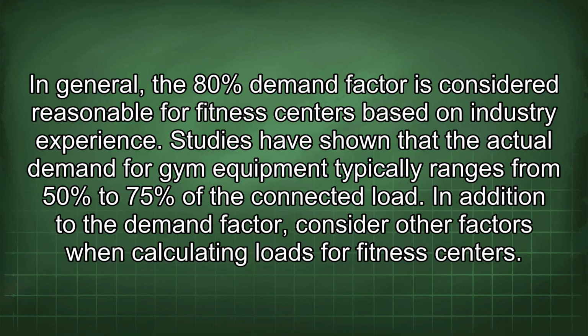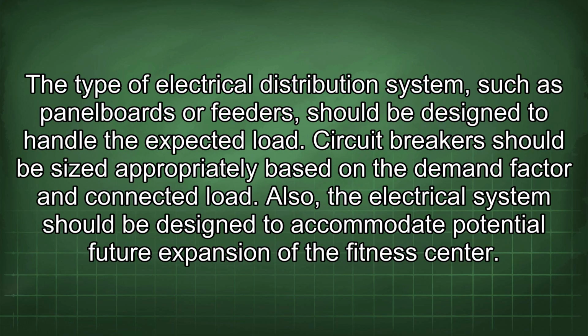In addition to the demand factor, consider other factors when calculating loads for fitness centers. The type of electrical distribution system, such as panel boards or feeders, should be designed to handle the expected load. Circuit breakers should be sized appropriately based on the demand factor and connected load. Also, the electrical system should be designed to accommodate potential future expansion of the fitness center.